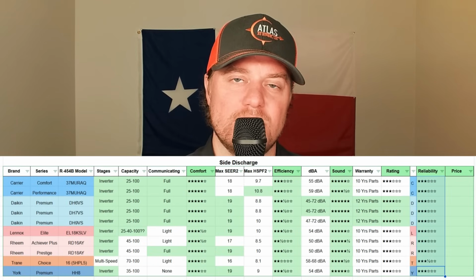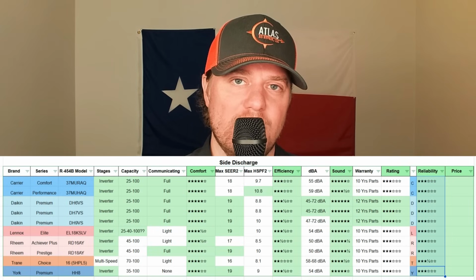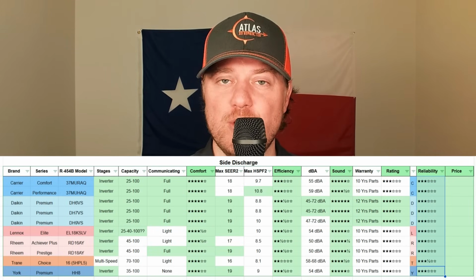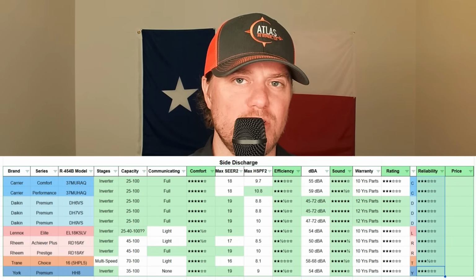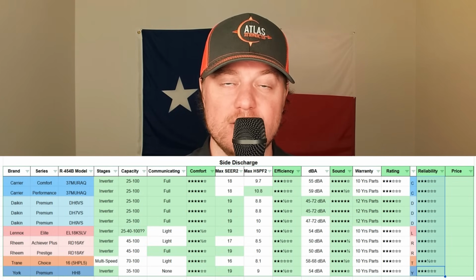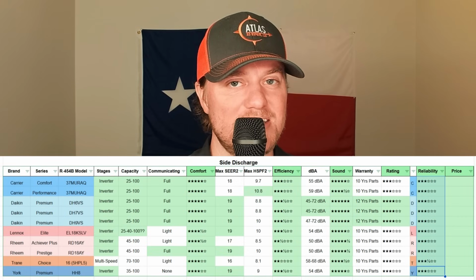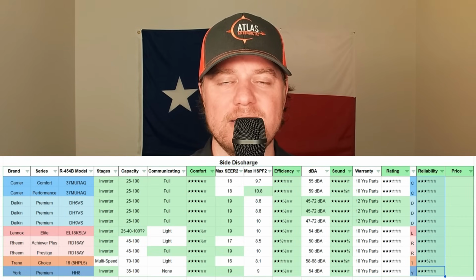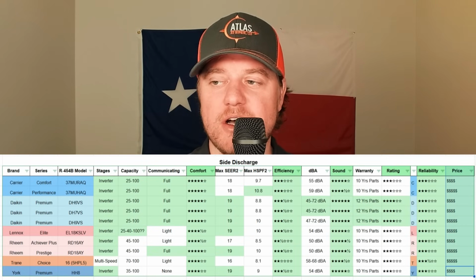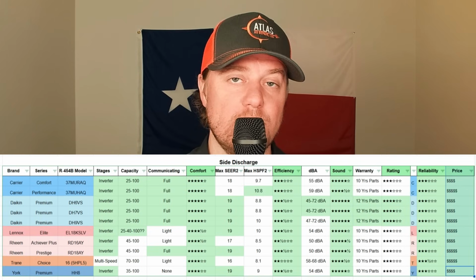Now when it comes to the question of who's going to be the most reliable, that's kind of going to be a hard question to answer, because for some of these manufacturers, they've only offered a side discharge unit for the last few years. Now my opinion on these units is I don't think that they're going to last as long as a top discharge unit, because physics says that every time you make something lighter, smaller, and more compact, it ends up wearing out faster. But at the end of the day, only time will tell. Now, when it comes to pricing, most of these are going to cost more than a two-stage system, and the cold climate models are going to be the most expensive.